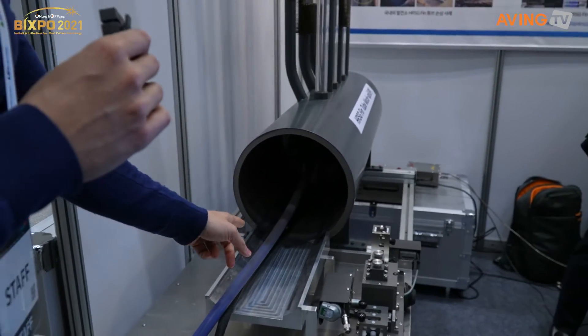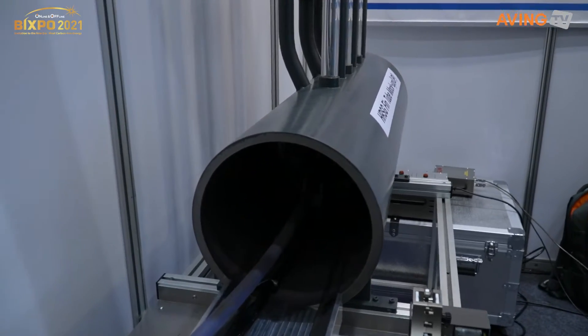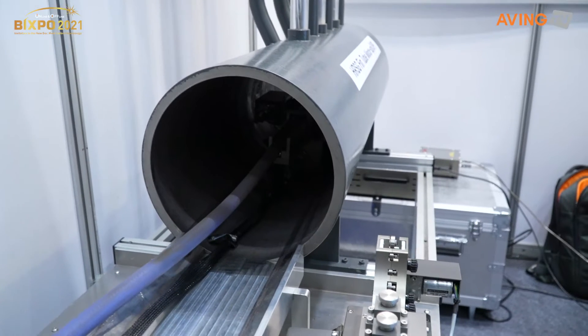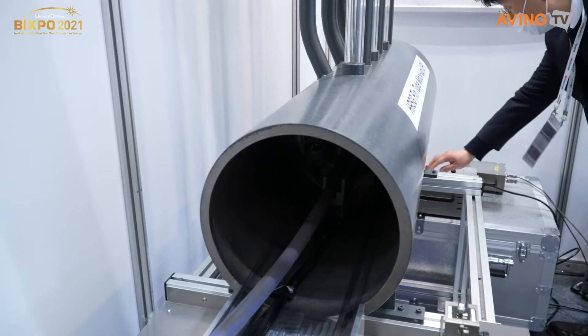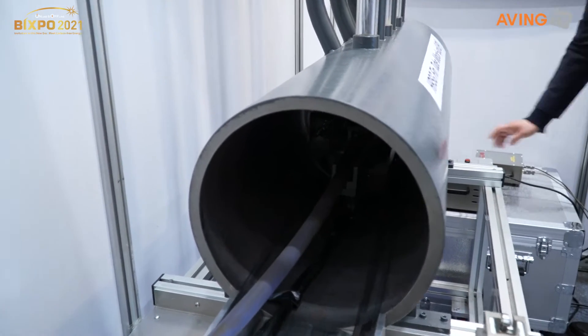Very quickly, this is what we're looking at. This is the HRSG fin tube — a mock-up of it. The sensor is now on the inside, and we're going to see it move through. It's actually going through right now, giving us information and also showing us a video of what's going on inside the tube.